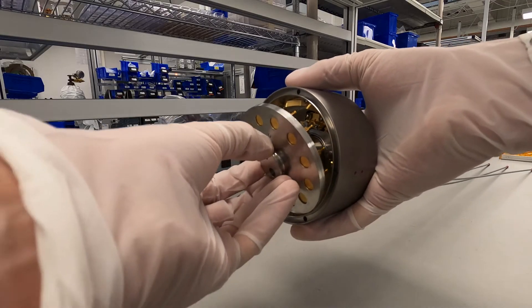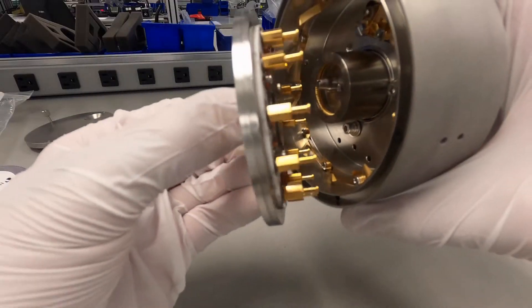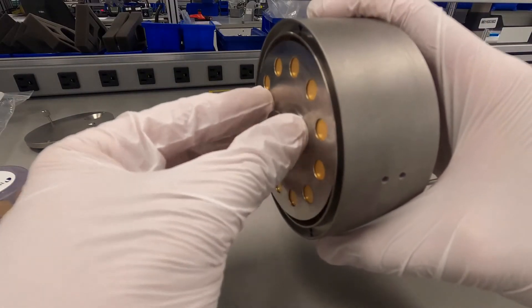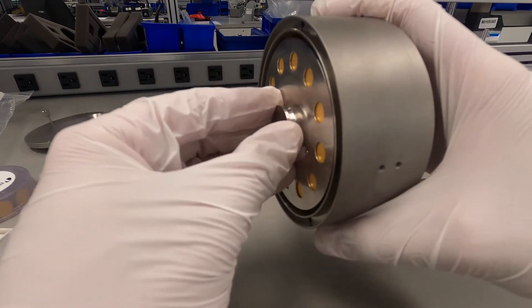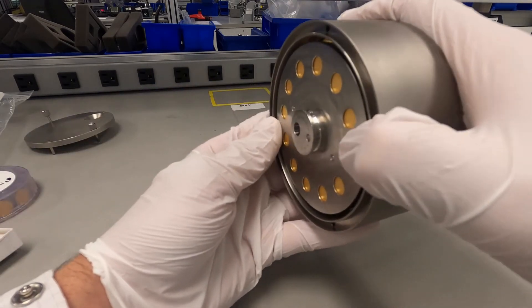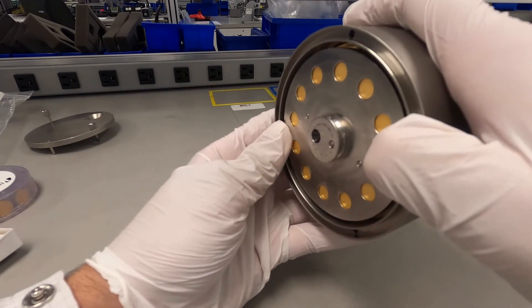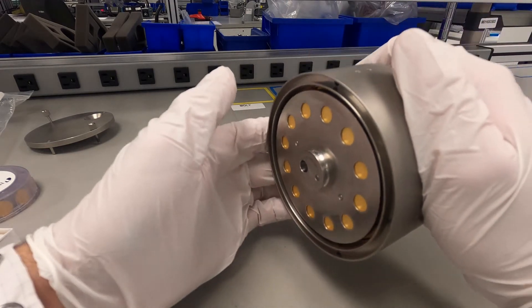To install the carousel assembly into the crystal 12 sensor, grasp the carousel assembly by the protruding hub and orient the locating hole of the carousel assembly with a number 6-32 location screw. The carousel assembly will snap into place.